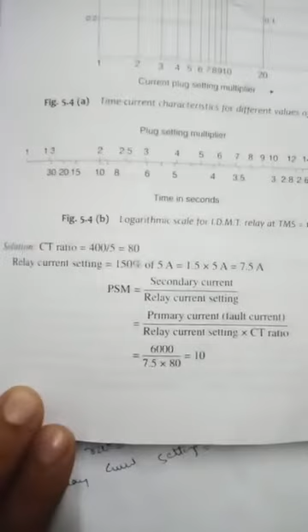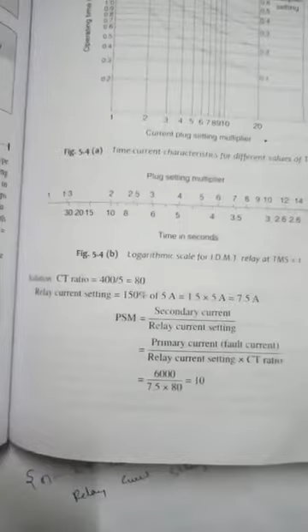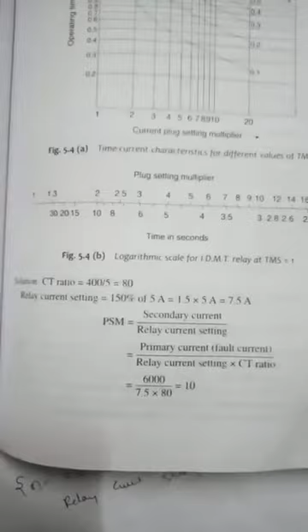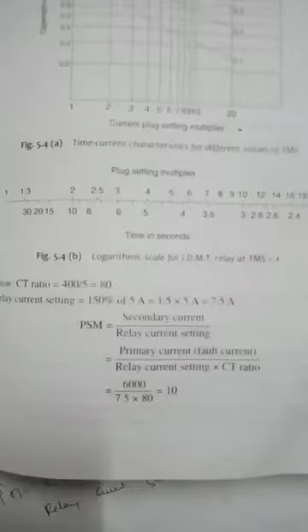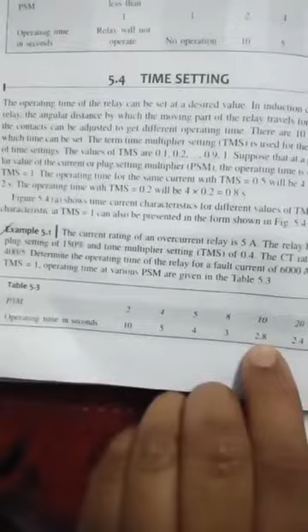Next, we are calculating the CT ratio as 400/5, which is 80. Relay current setting is 150% of 5 amps, that is 1.5 into 5, 7.5 amps. PSM is given as secondary current divided by relay current setting, that is primary current by relay current setting into CT ratio. So when you substitute the value of primary current as 6000 given in the question, relay current setting as 7.5 and CT ratio as 80, the PSM value you get is 10. Operating time from the table for PSM of 10 is 2.8 seconds.